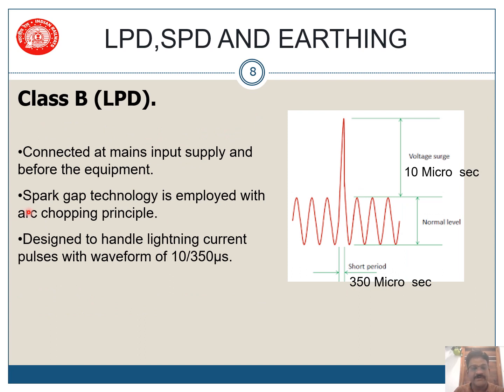Now coming to class B protection, it is connected to the mains input supply, before the equipment. It is connected to the mains input supply, that is the 230 volt supply which you bring. The technology generally used is spark gap technology, which is employed with an arc chopping principle, that is cutting out the lightning. It is designed to handle lightning current pulses with a waveform of 10 by 350 microseconds.